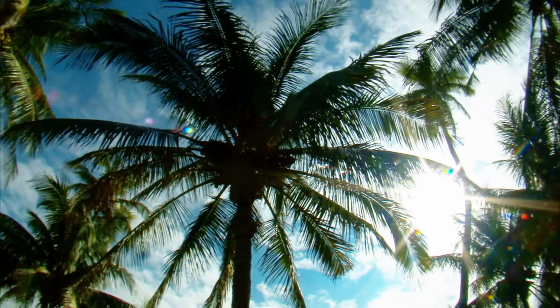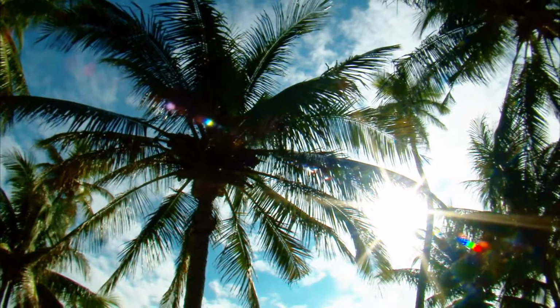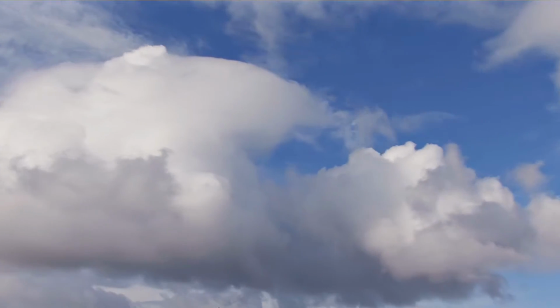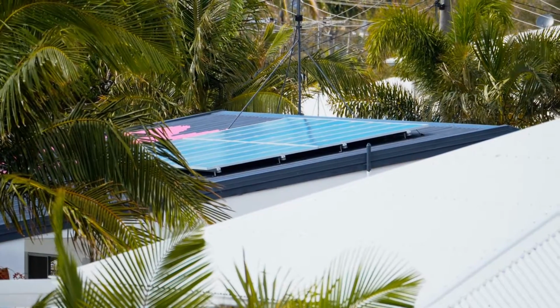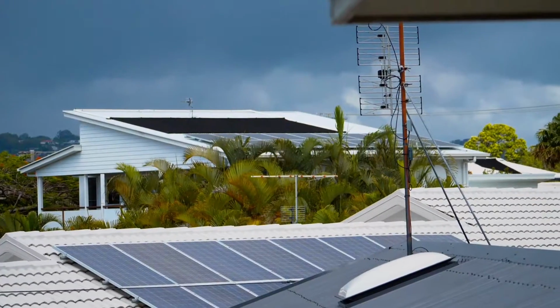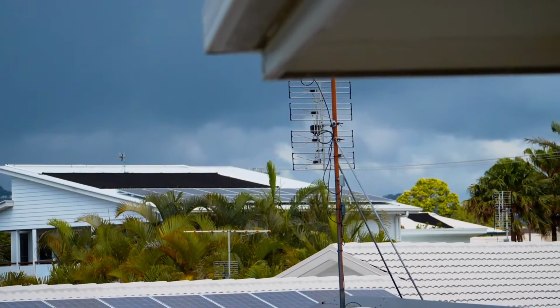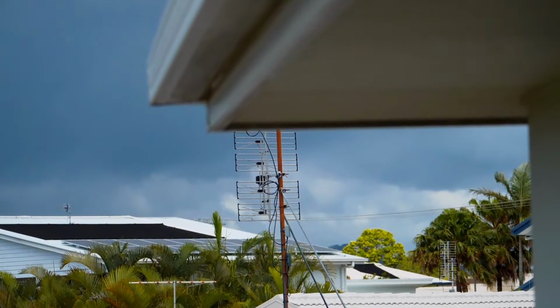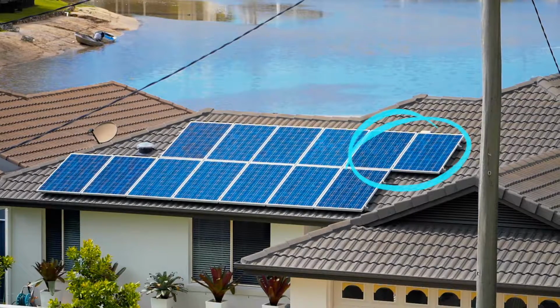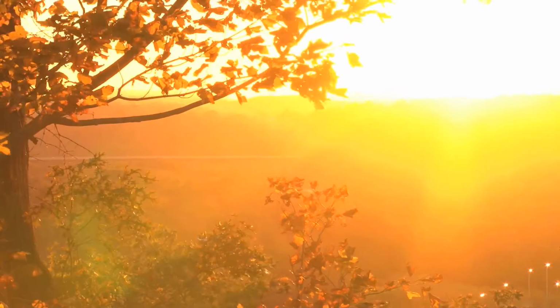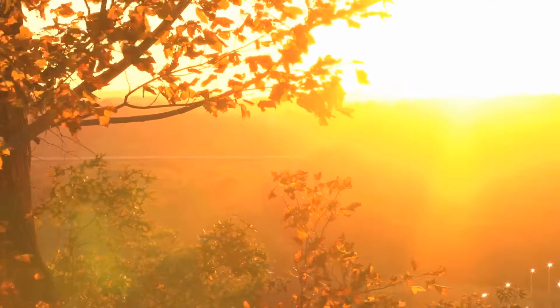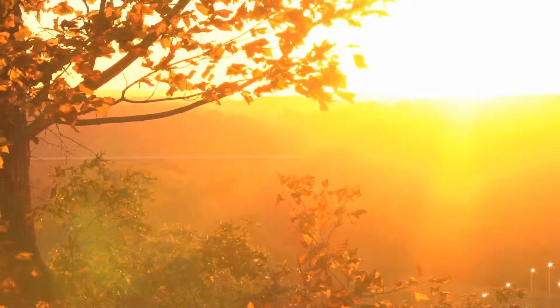Shade is by far the most common cause of reduced power generation. It can occur rapidly with cloud cover, or much slower over years as those big trees start to impede the view of the sun. Buildings and other structures may also be responsible for shading and will reduce sunlight on your panels. Even one panel partly shaded will have a dramatic effect over the overall performance of your system. And don't forget seasonal variations as the sun sits higher or lower in the sky. So please be sure to check for obvious causes of direct shading on your panels throughout the year.